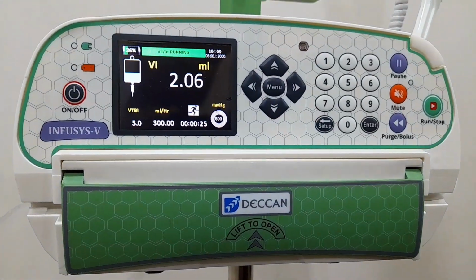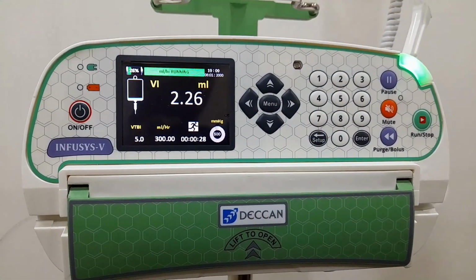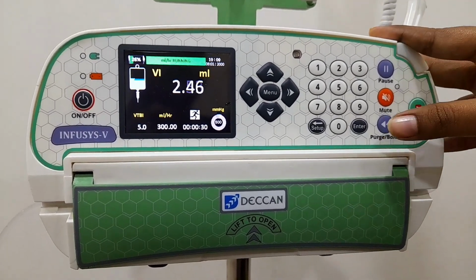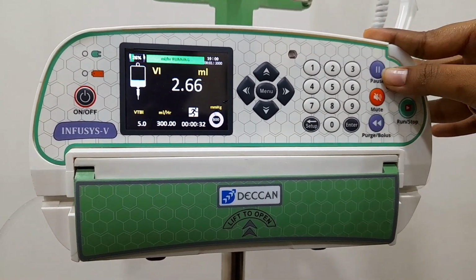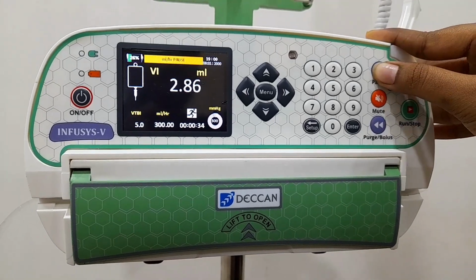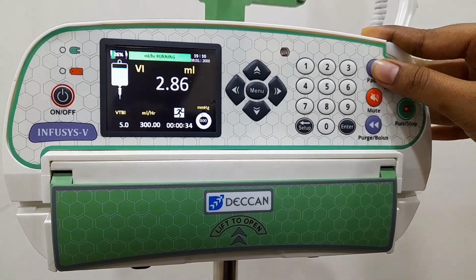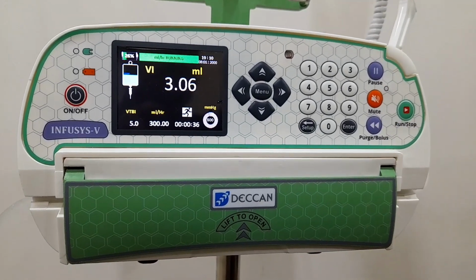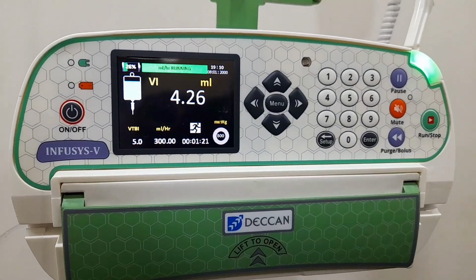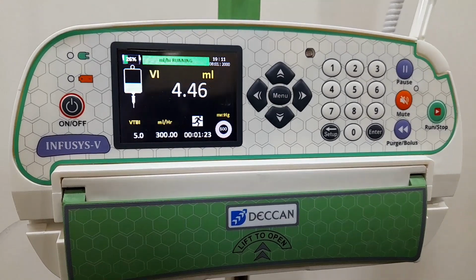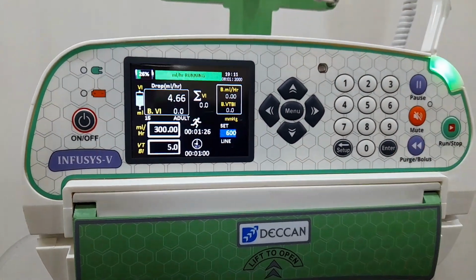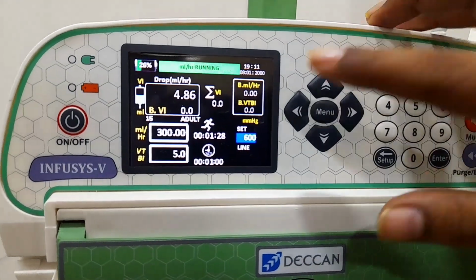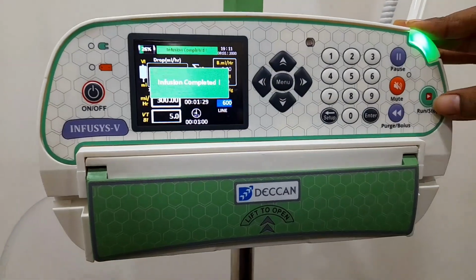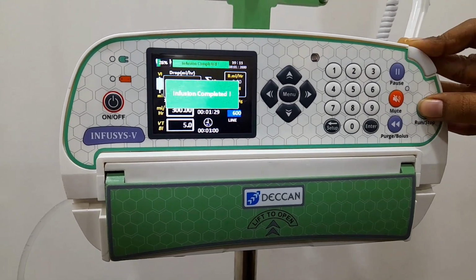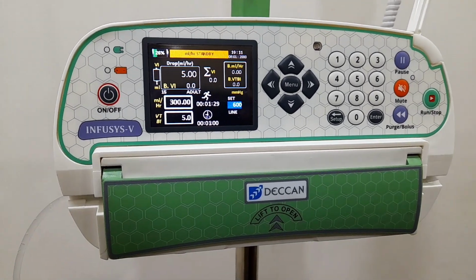Now it automatically switched to the innovative multi-layer screen. In this condition, we can see the pause option. Using the pause key, we can pause the function, and using the same pause key, we can resume it. We all know that when the infusion gets closer to the target volume, the nearing volume limit pre-alarm occurs. The nearing volume pre-alarm occurred, and also the infusion completed pop-up. So now we can stop the unit using the run/stop key.